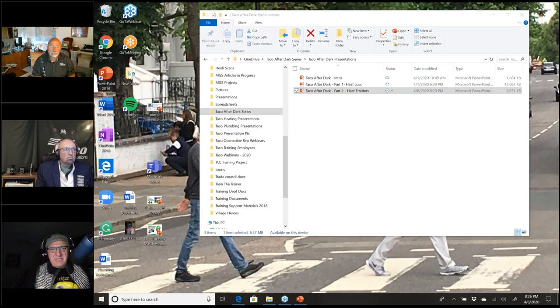A delta P pump, you said, the words you used, which are interesting, change the pressure. That's not exactly what they do. They react to pressure changes in order to maintain a pressure differential. So if a zone valve opens, say the pump's pumpulating along, and a zone valve opens, that means there's less resistance against that impeller. That's a signal for the circulator to speed up. There's less resistance, that means something's opened up. I'm going to giddy up and go faster.